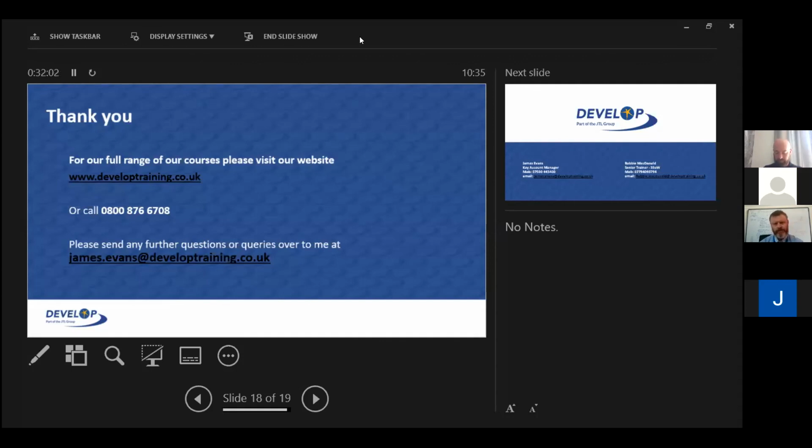So I'm pleased actually that the IET have now issued this and pointing out to lots of people that it's all based upon risk assessment. And you're quite right. If you take a welding shop or a fettling shop in a factory and you've got portable equipment thrown around the ground, grinders and all the rest of it, well, they should be checked every time before they're used, all the time. They should also be checked probably on a periodic inspection. I might put it as 3 months.